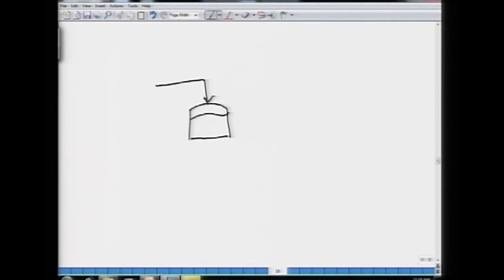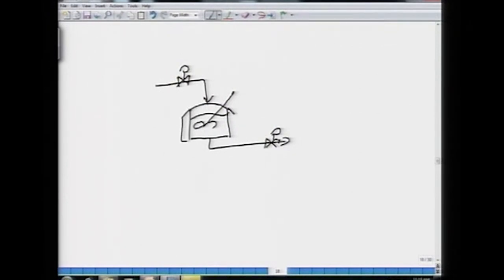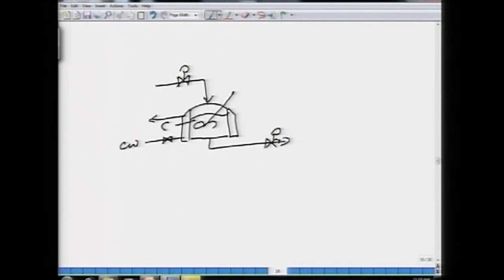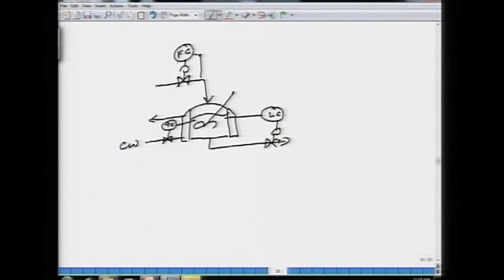Products and reactant mixture are flowing out; the reaction is exothermic so I have a jacketed CSTR with heat removed by circulating cooling water. I am controlling the temperature by adjusting the cooling water flow rate, and the level is being controlled by adjusting the outflow — this is under flow control. If the set point of this inflow is increased or decreased, meaning the flow rate changes, the temperature of the reactor will also get disturbed.